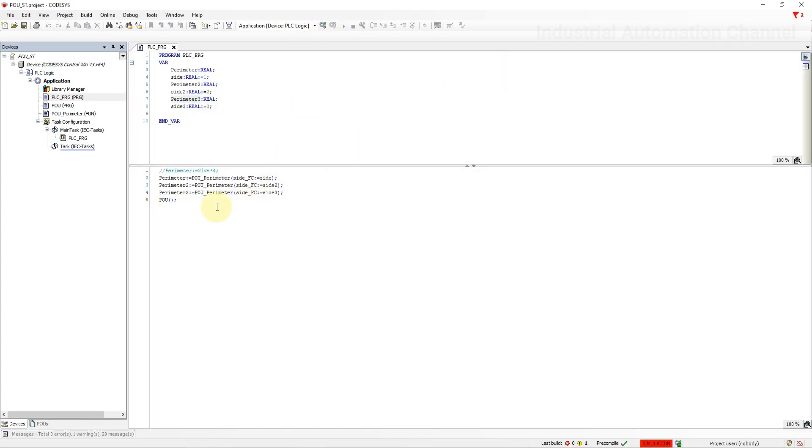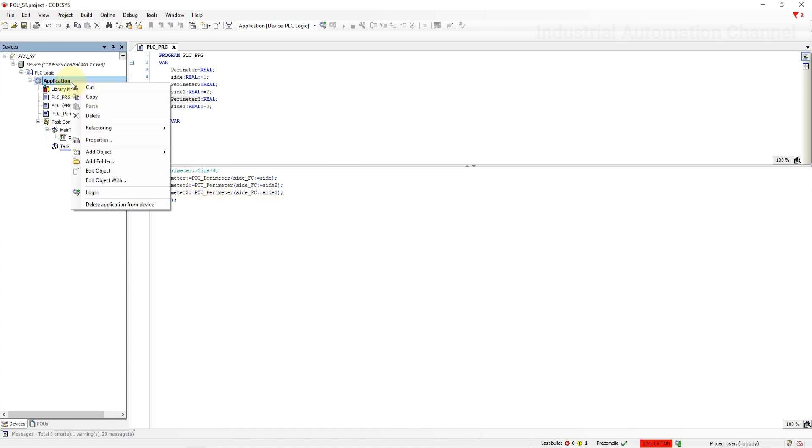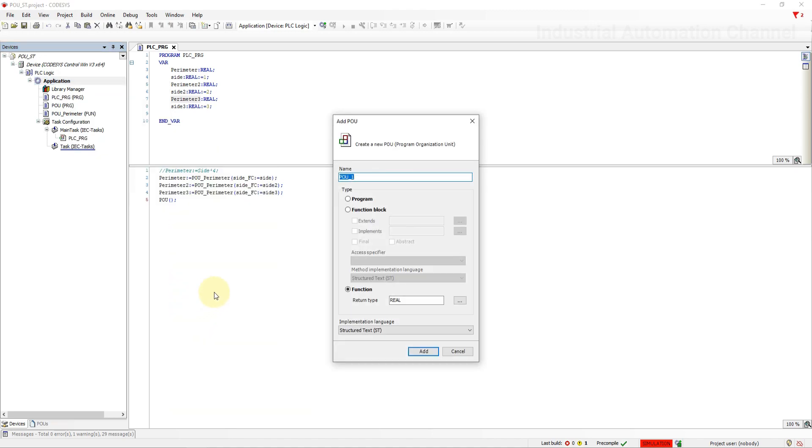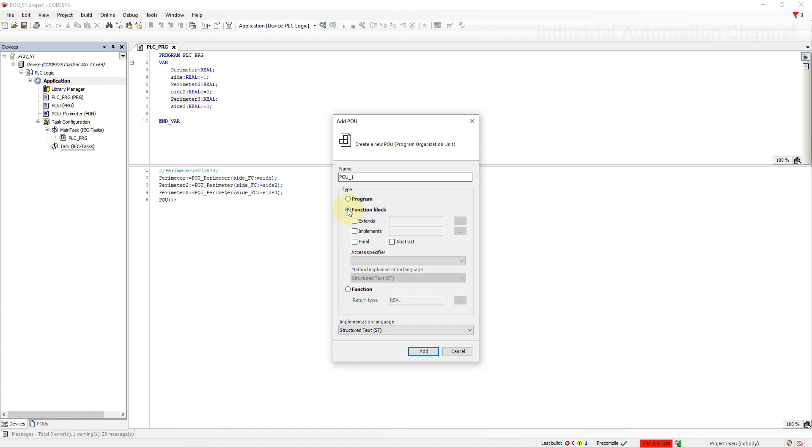The third POU is the function block. The main difference between function and function block is that function does not have persistent data. So it is used to do some tasks and at most return a value or output and the data will not be stored for the next scan. But function block can save its data and they can be used for the next cycle.